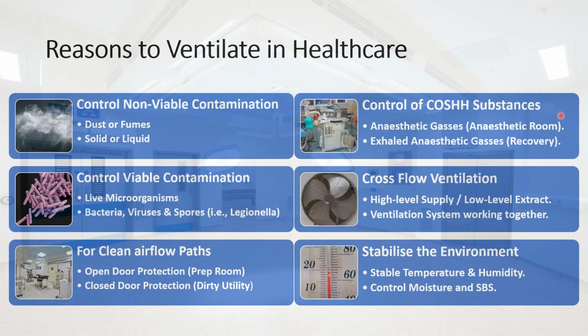The fourth reason is for COSHH, substances such as anaesthetic gases, and you've got to consider as well exhaled anaesthetic gases in recovery spaces. As the patient breathes out the anaesthetic gas that they may have been breathing in for a couple of hours, it's important that the mechanical ventilation system takes that away and it isn't projected straight into the breathing zone of a recovery nurse. And the way that we do that is the next box, cross-flow ventilation. We take a high-level supply and a low-level extract in anaesthetic rooms and recovery spaces. Gas is denser than air and it will drop and be drawn away by the mechanical ventilation system. It's important that the two systems work together and they don't interact with one another and cause issues within the space.